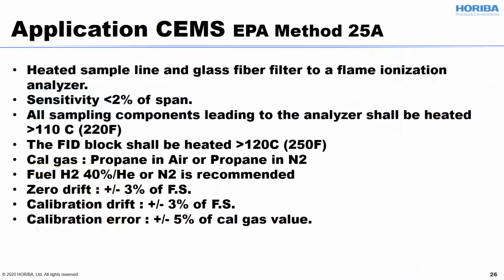US EPA defines the measurement method for the total hydrocarbons by flame ionization detection. The number of the standard method is 25A. Basically, this is applied for the continuous measurement. Let me review what the requirements are. Sensitivity has to be within 2% of span.